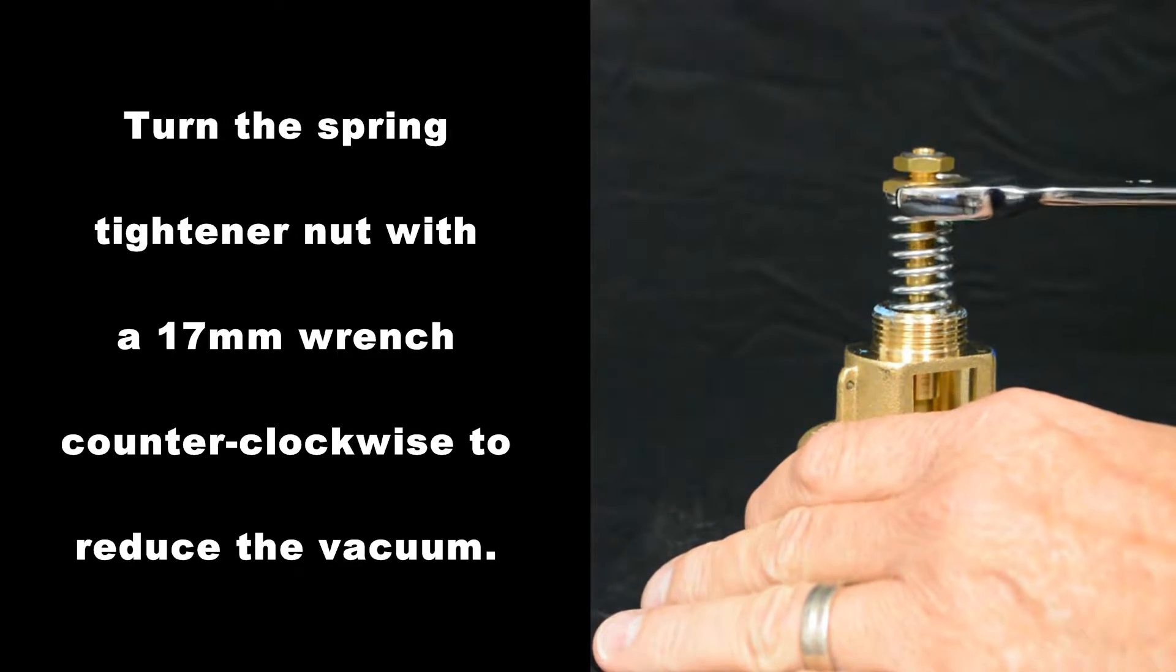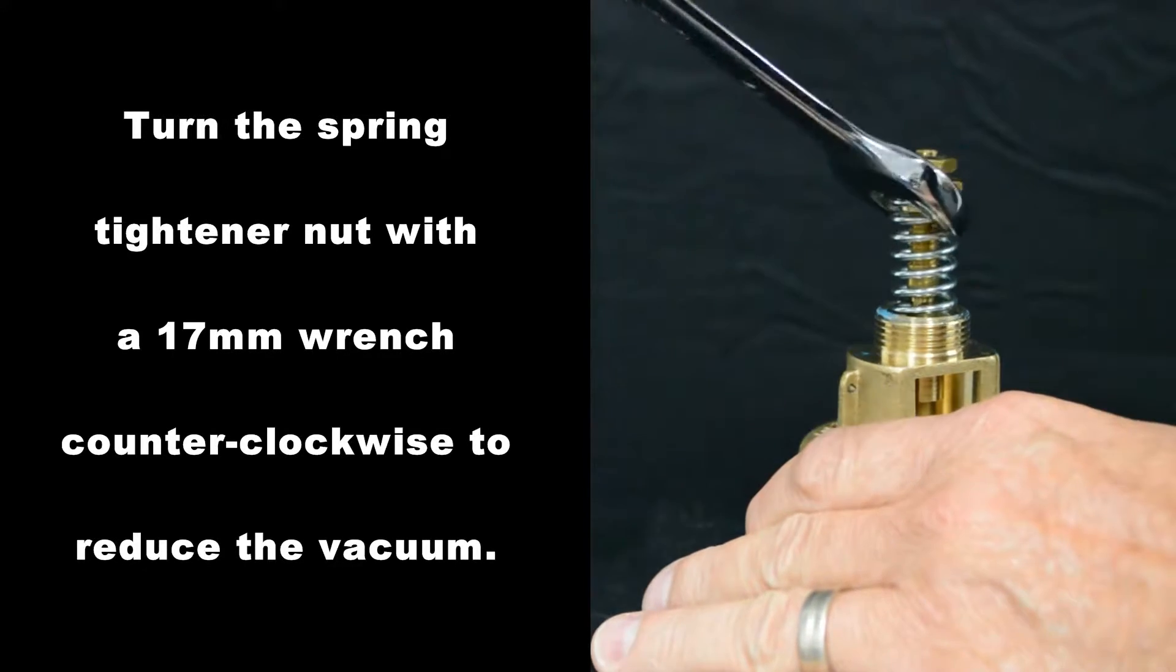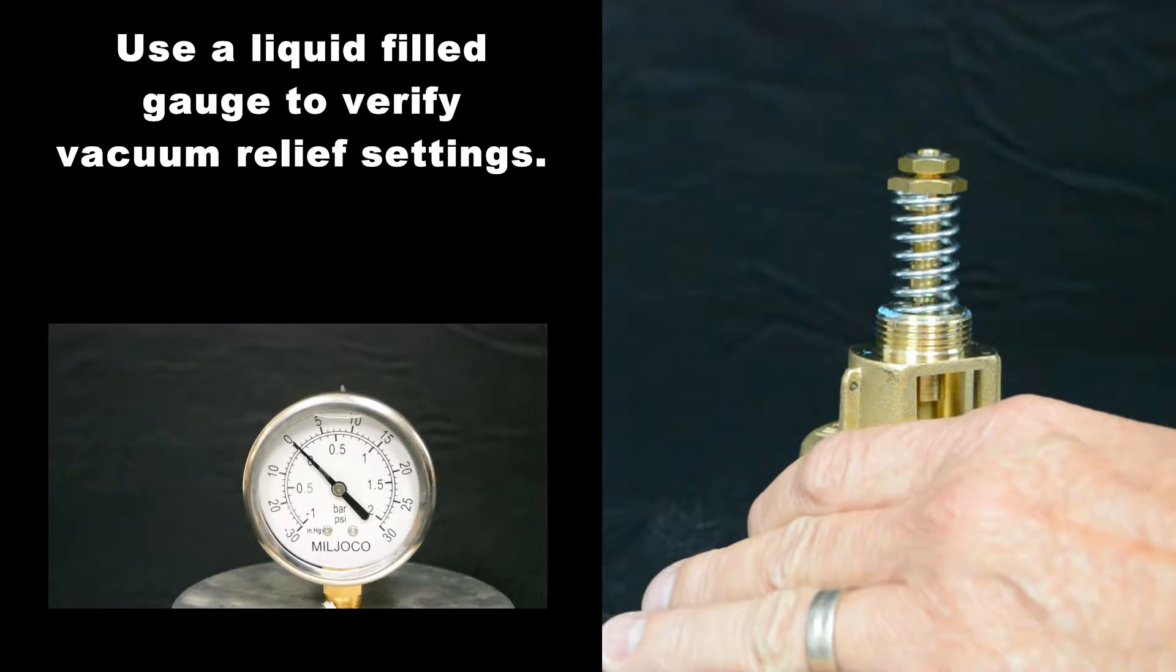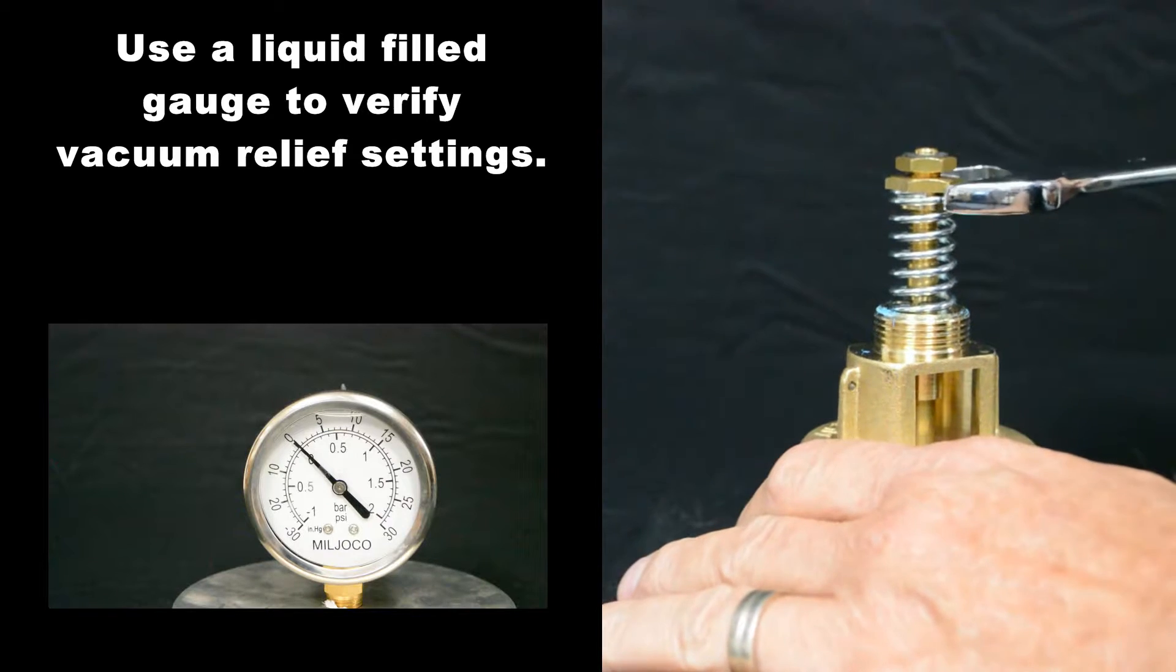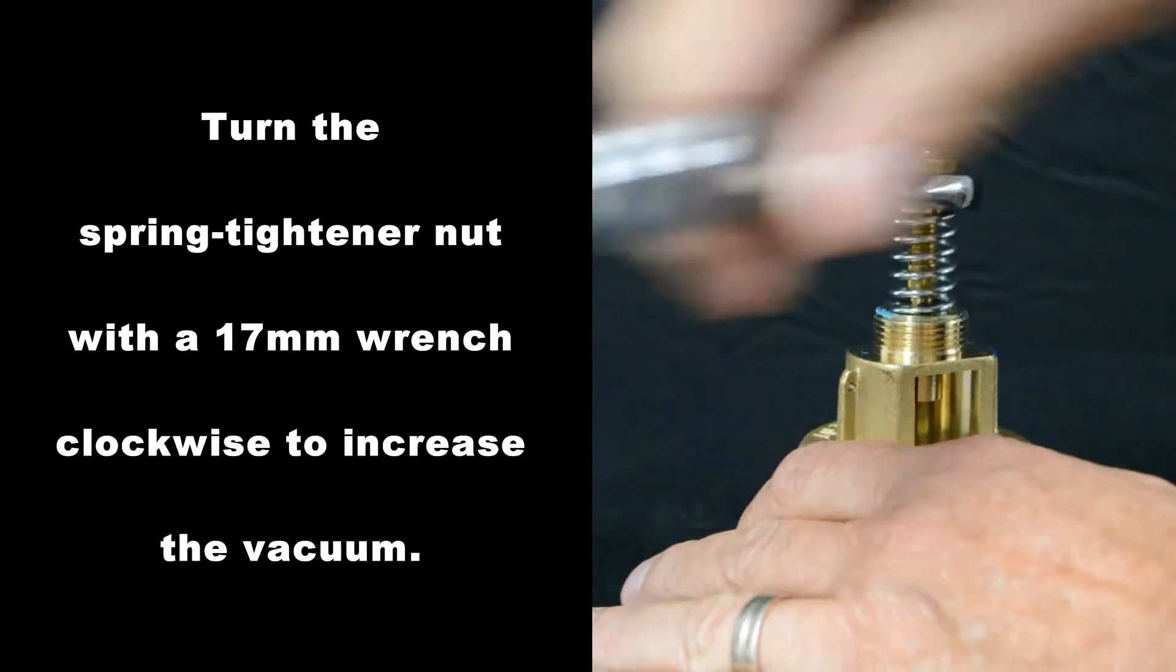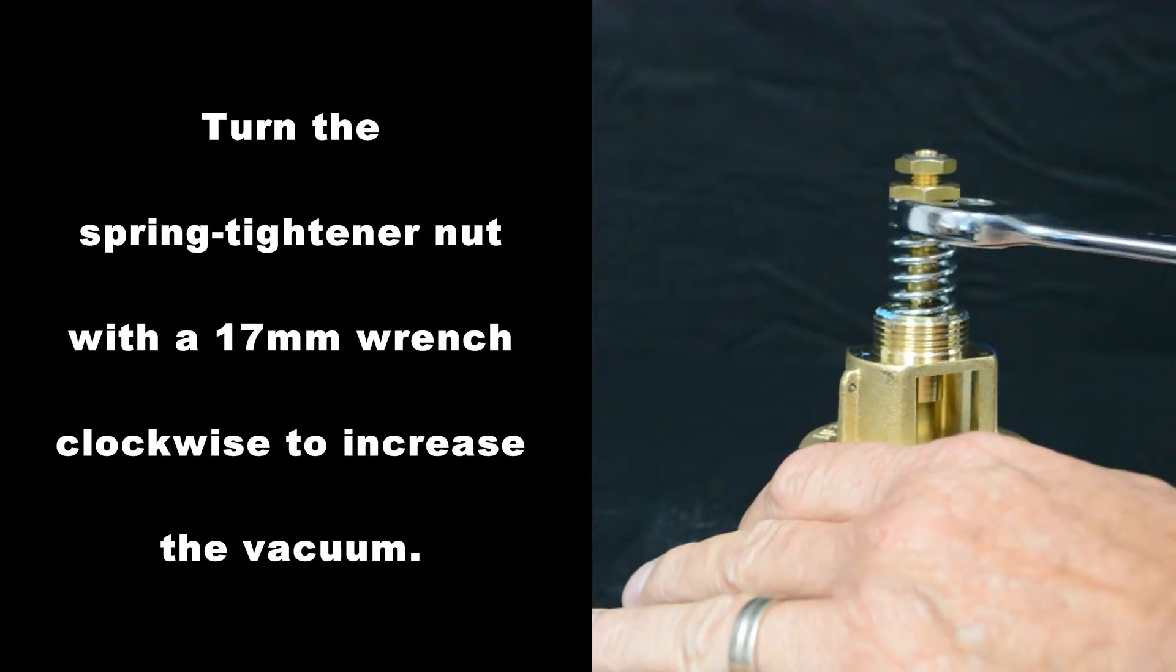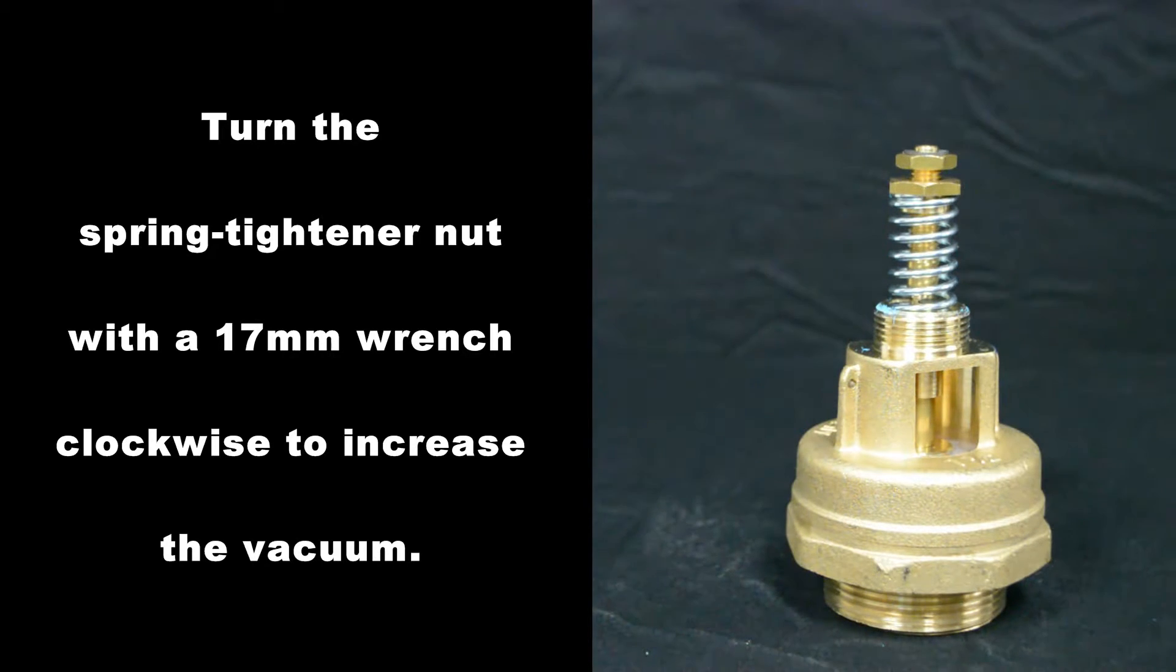Turn the spring tightener nut with a 17mm wrench counterclockwise to reduce the vacuum. Use a liquid filled gauge to verify vacuum relief settings. Turn the spring tightener nut with a 17mm wrench clockwise to increase the vacuum.